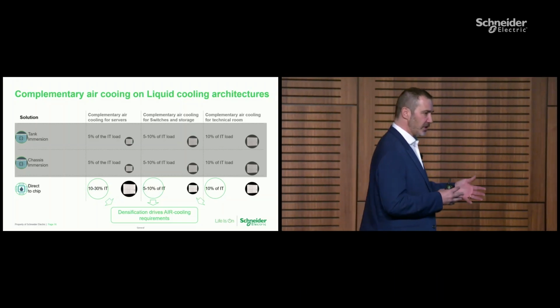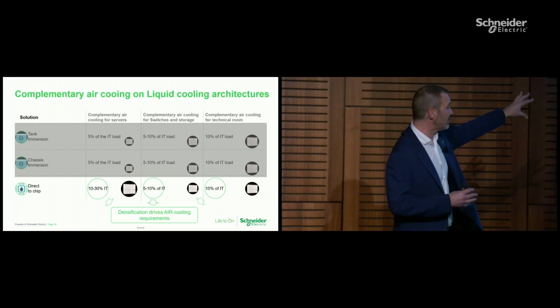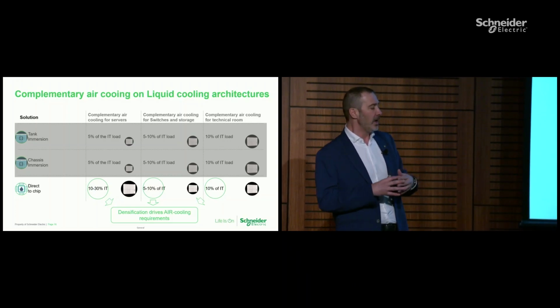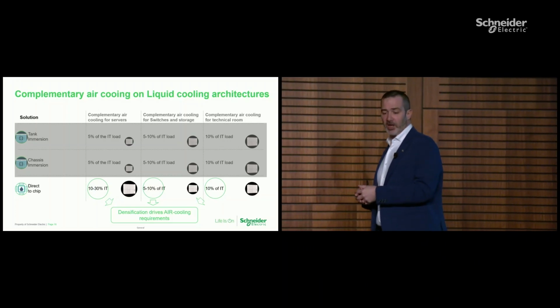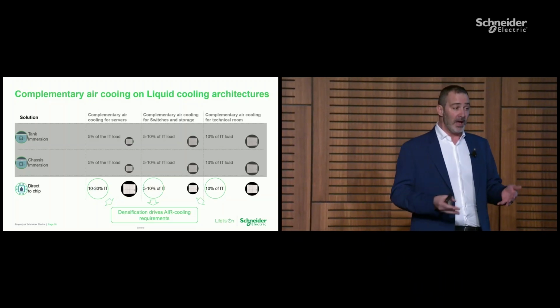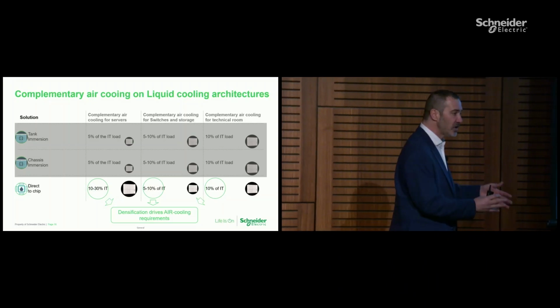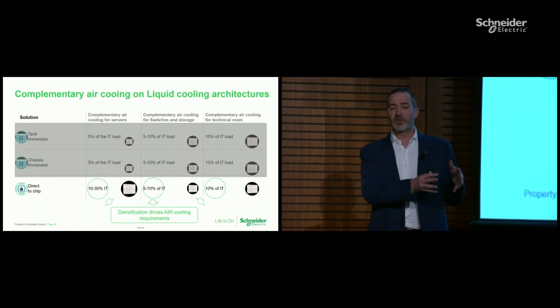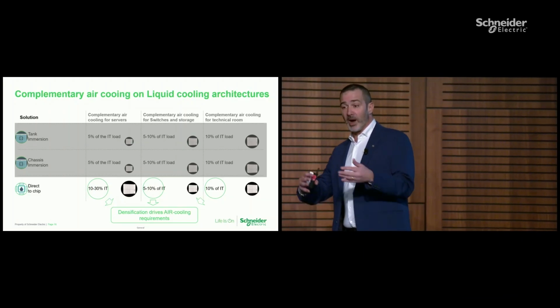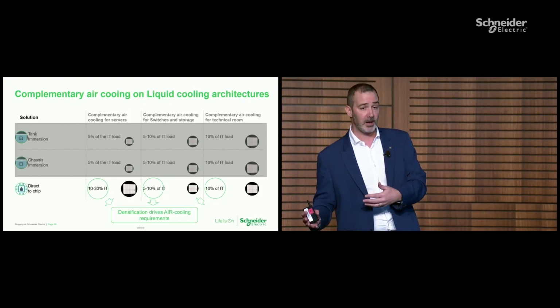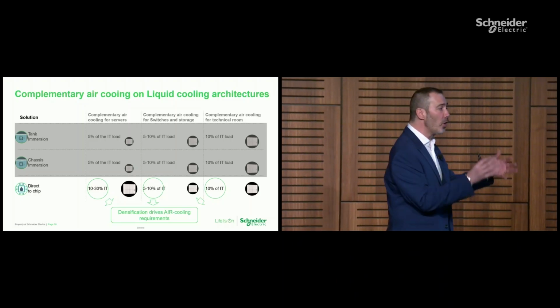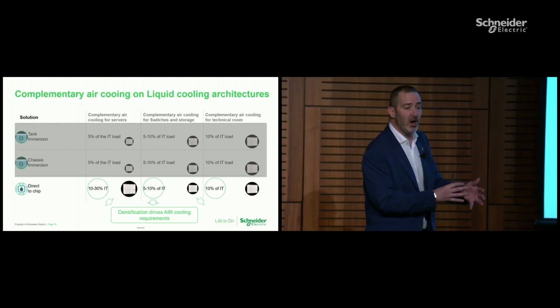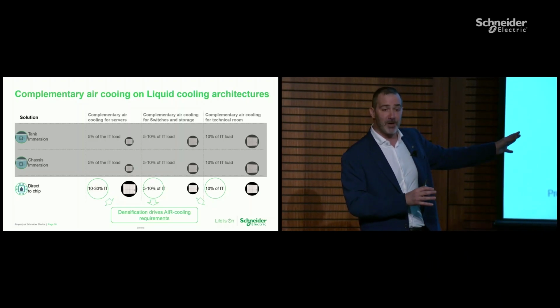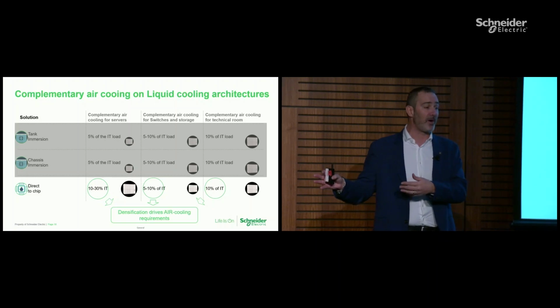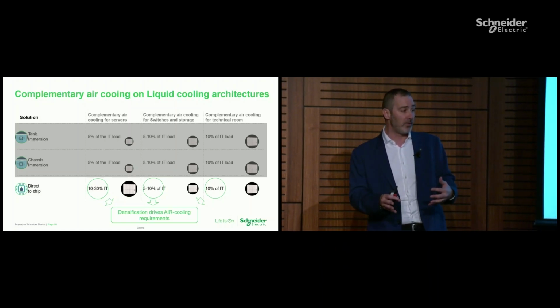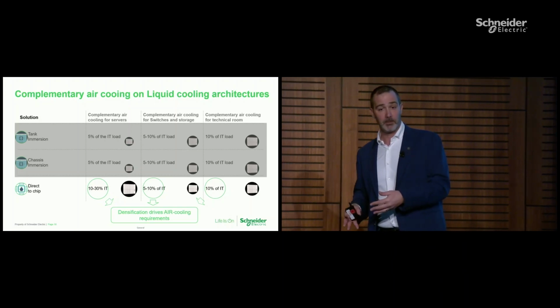We cannot under-evaluate this, because in parallel with this single-digit or low double-digit percentage, we need to combine it with densification. And densification is moving the capacity, the density, from the current 10-15 kilowatt per rack to 150-200 kilowatt per rack. So if today with air cooling you need to dissipate 15 kilowatt per rack, even if you remain at 10% of 150 kilowatt per rack, you are at the same level or above the level of air you have today.